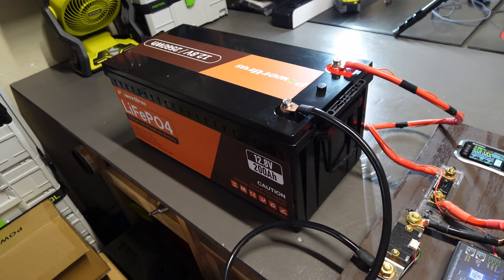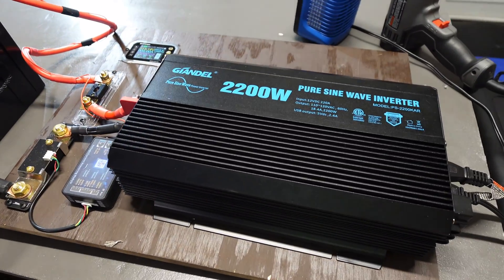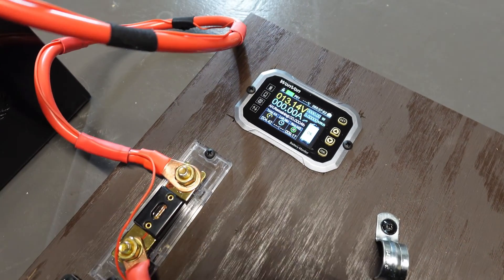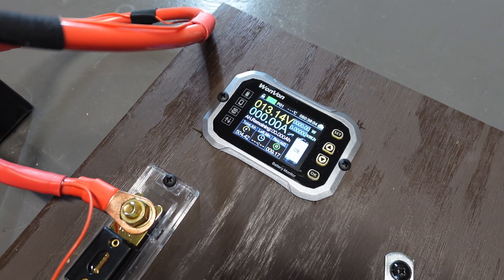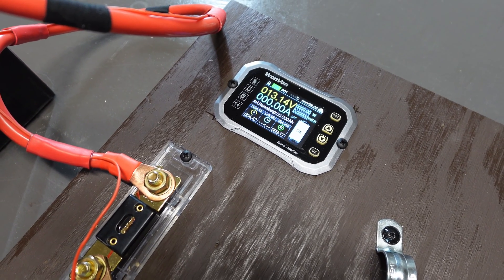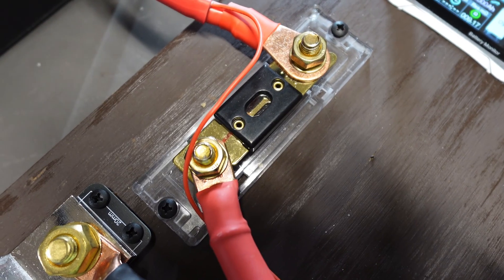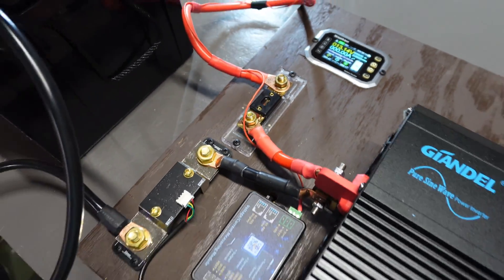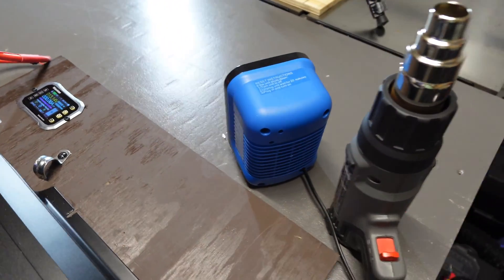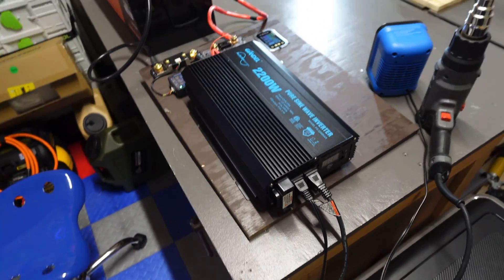The setup here: I've got the battery hooked up to my 2200 watt Giandel inverter with all the shunts in line, so we'll be able to monitor the amperage coming out of the battery to see how close we can get to 200 amps without popping that 175 amp fuse. For our devices, I've got a 1500 watt heat gun and a 500 watt space heater, both hooked up to the inverter. Let's get this test going.